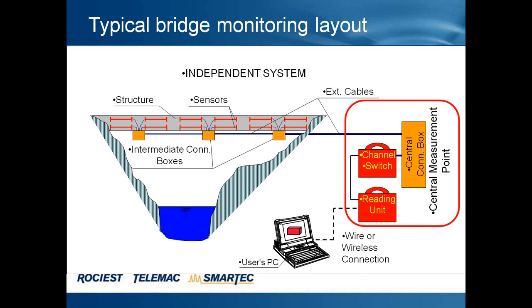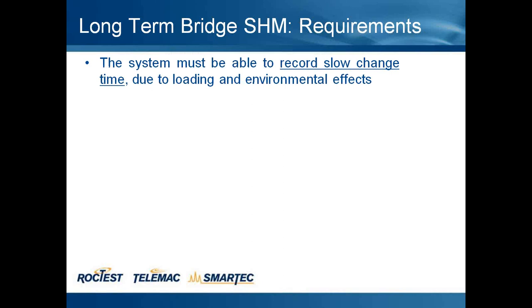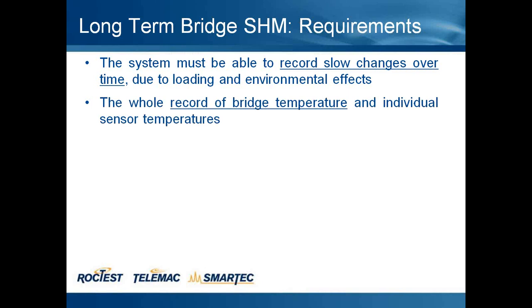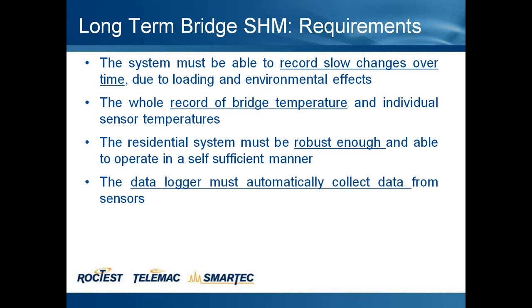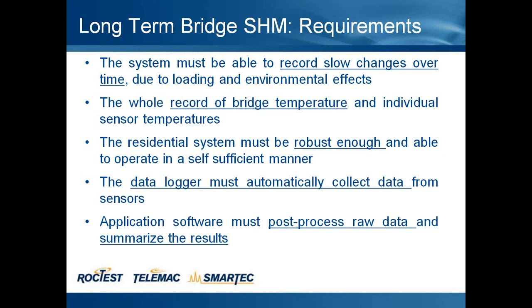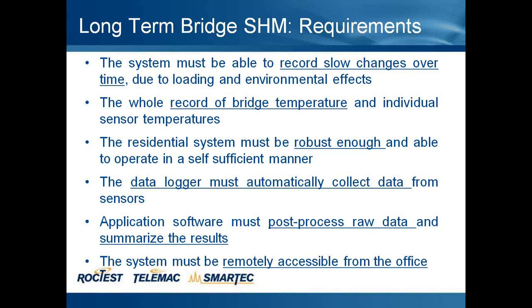What are the requirements of a long-term bridge structural monitoring system? First, the system must be able to record slow changes over time due to loading and environmental effects. It must also record bridge temperature and individual sensor temperatures. The system must be robust enough and able to operate in a self-sufficient manner. The data logger must automatically collect data from sensors, and application software must post-process raw data and summarize the results. Finally, the system must be remotely accessible from the office.